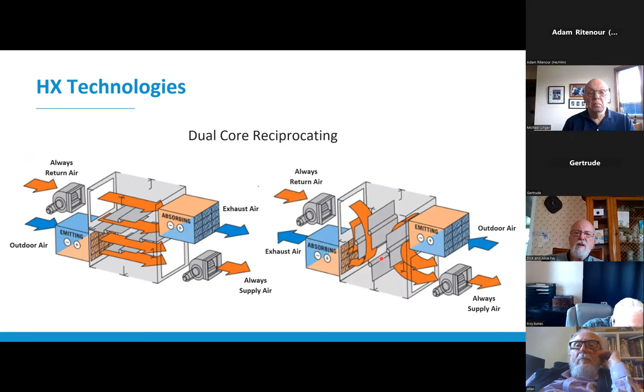And then those dampers flip every 60 seconds. So now this return air is being diverted to that bottom core, which is now absorbing the heat from that return air before it's exhausted to the outside. And then for the top core, that outdoor air is picking up the heat from the emitting core before it's being delivered to the building.